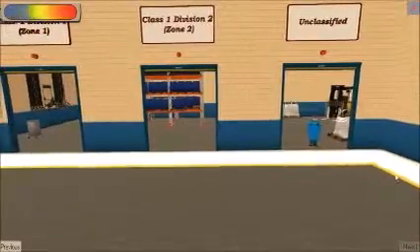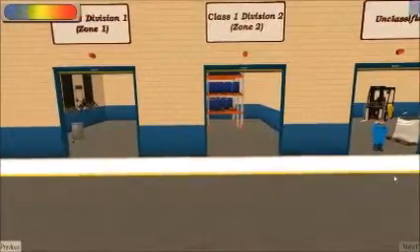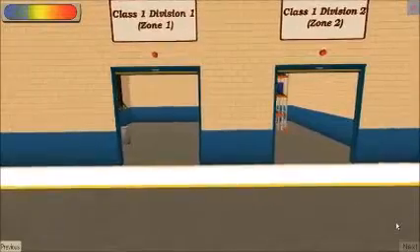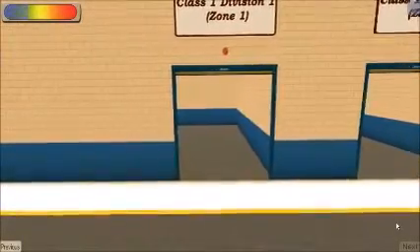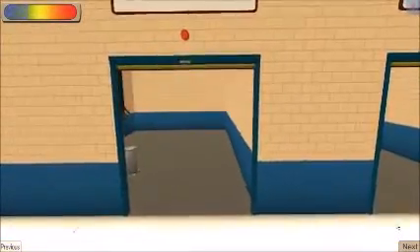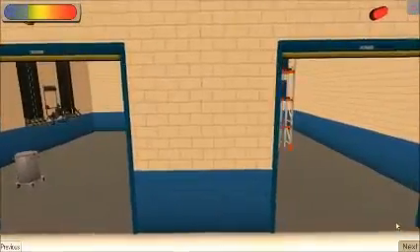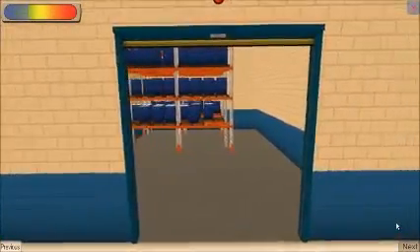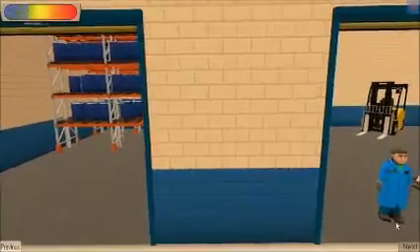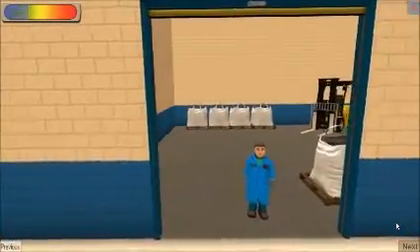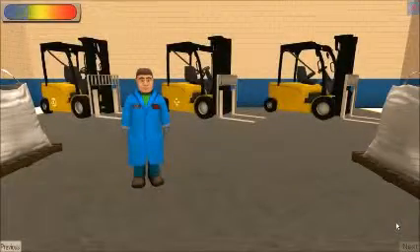I want to take a drum filled with acetone from the Class 1 Division 2 or Zone 2 area into the Class 1 Division 1 or Zone 1 area, so I can transfer the acetone into a safety can. I will not be switching lift trucks in between the classified areas. Which lift truck is the proper one to use?